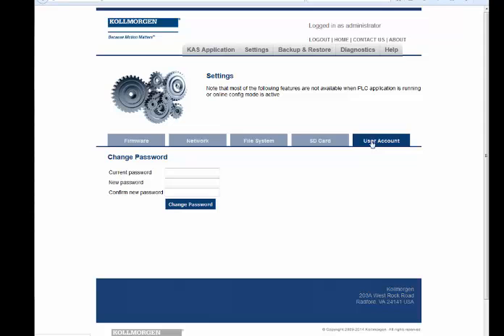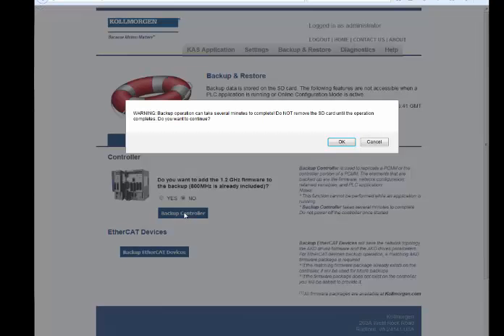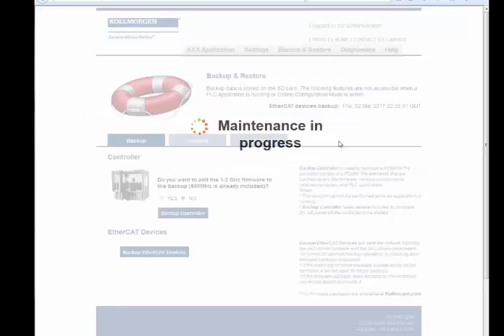In the Backup tab, both the controller and EtherCAT devices can be backed up to the SD card. Backup controller is used to backup the PCMM or the controller portion of the PDMM for storage or loading into another controller. The backed up elements are firmware, network configuration, retained variables, and application code. The backup can take several minutes to complete. The LED segment will sequence during the download. Do not power off the controller once started until completion.